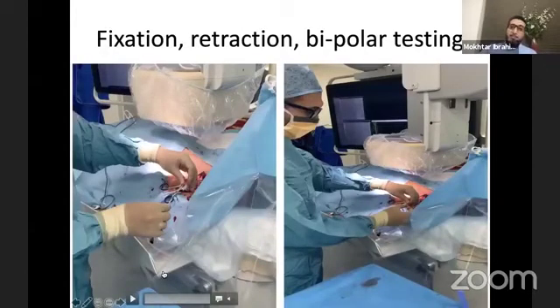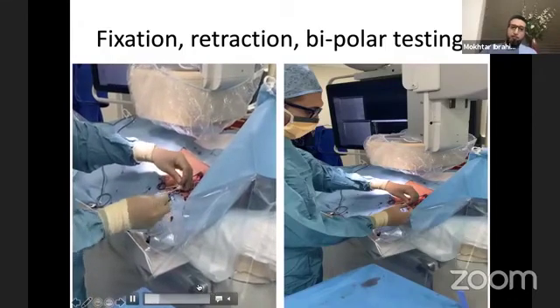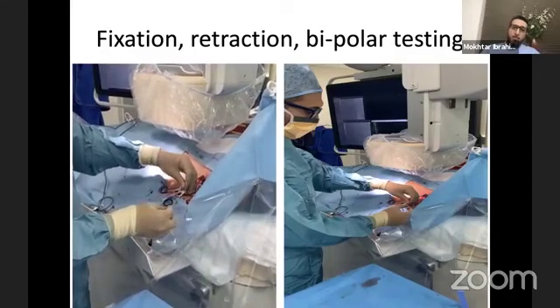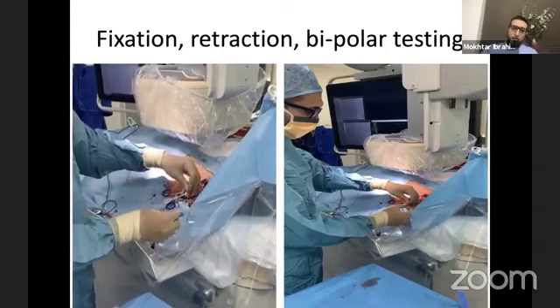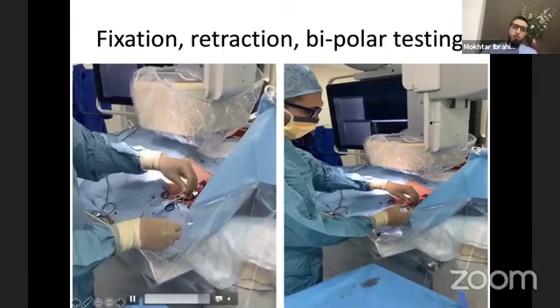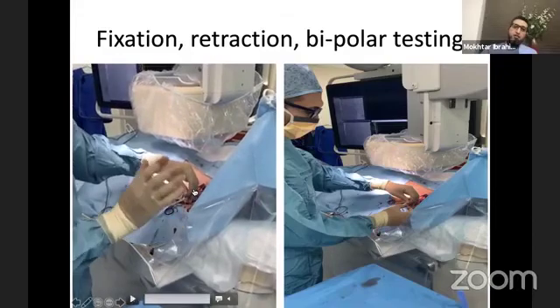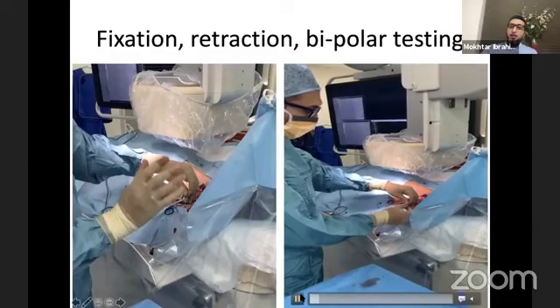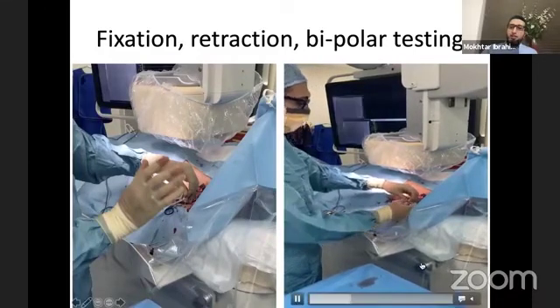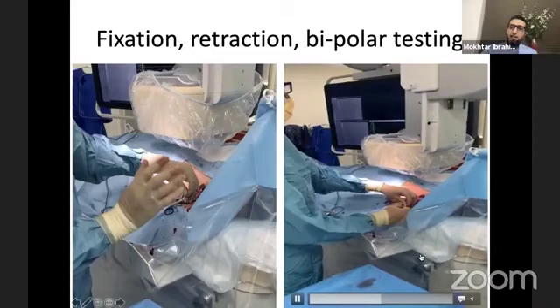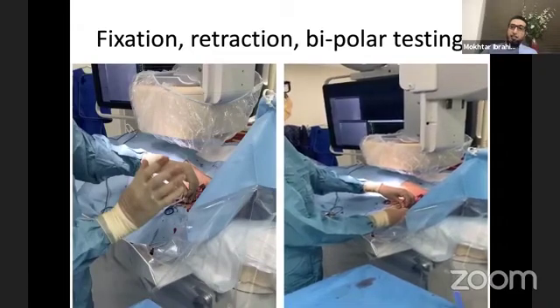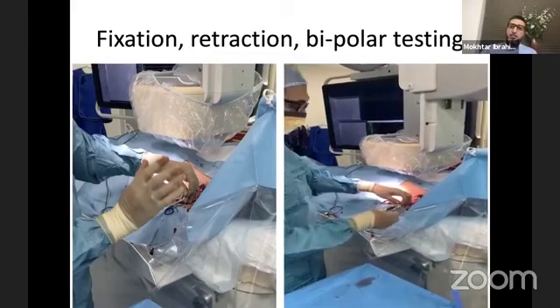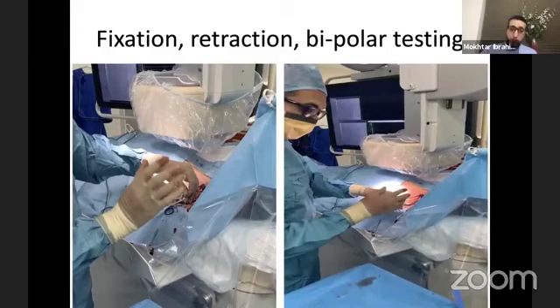So how do we fix this lead? This lead, as I mentioned, has a screw, an active helix. So what I normally do is 4 to 5 turns with your right hand clockwise, 1 turn, hold with your left hand. Look at my left hand, please. So 4 turns or 5 turns, and normally you get the screw, the lead screwed into the septum. And then I need to retract my catheter a little bit, fix the lead and retract the catheter to expose the second pole of the lead, and then we test the lead in bipolar configuration.